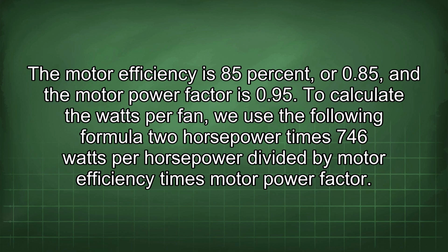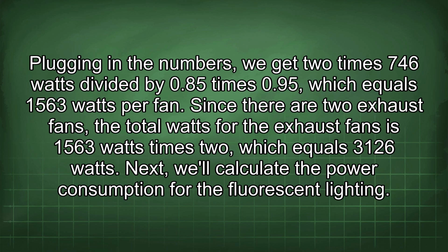To calculate the watts per fan, we use the following formula: 2 horsepower times 746 watts per horsepower divided by motor efficiency times motor power factor. Plugging in the numbers, we get 2 times 746 watts divided by 0.85 times 0.95, which equals 1563 watts per fan. Since there are 2 exhaust fans, the total watts for the exhaust fans is 1563 watts times 2, which equals 3126 watts. Next, we'll calculate the power consumption for the fluorescent lighting.